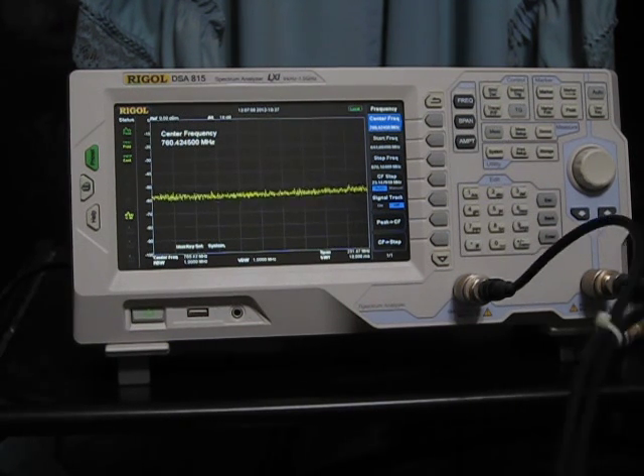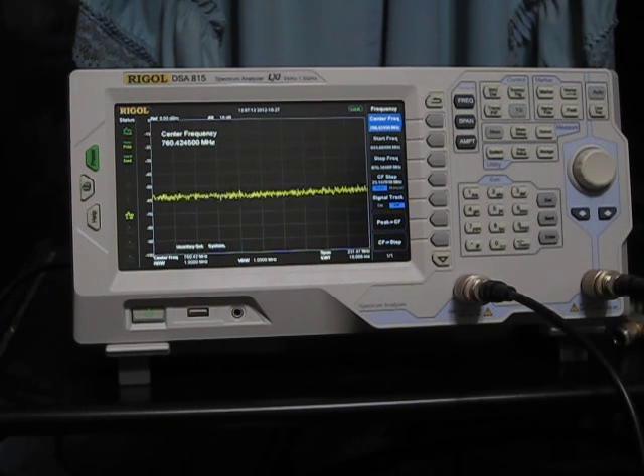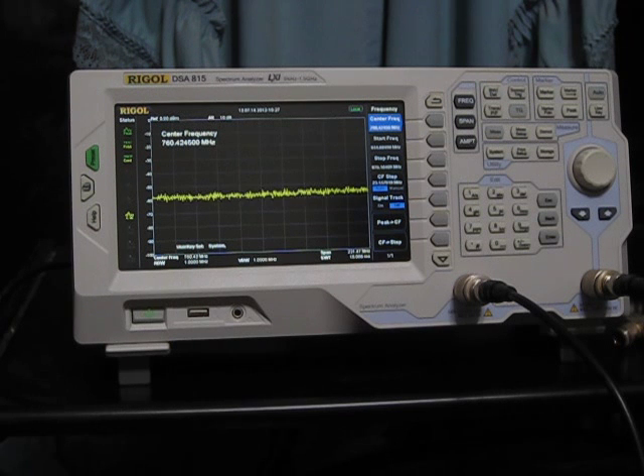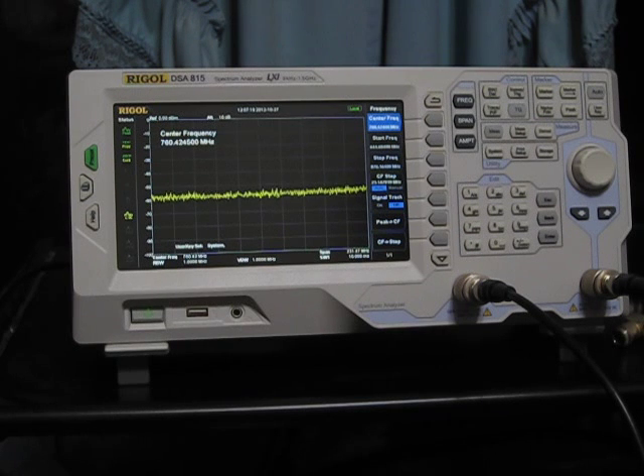First thing we did is we're going to hook the cables that we're going to use to do this. We've hooked the tracking generator output to the input so that we can normalize the spectrum analyzer with this cable arrangement. That's a very important thing to do.